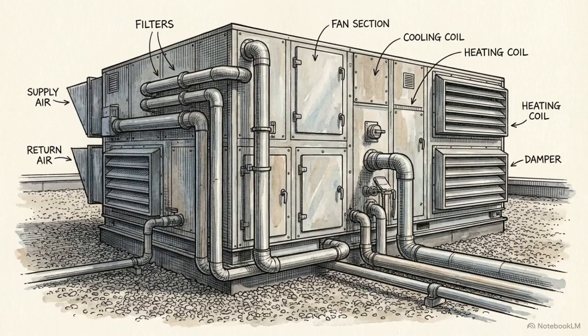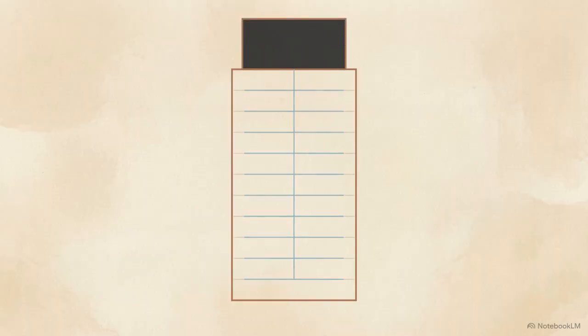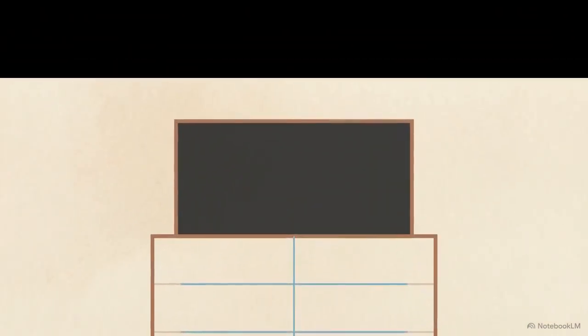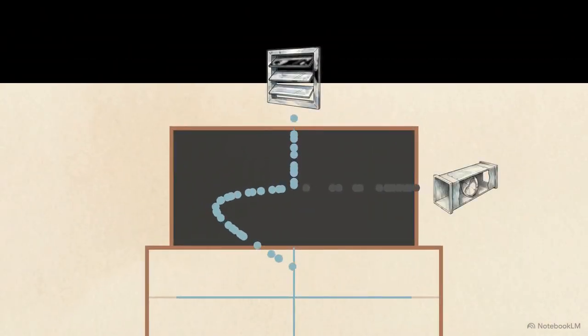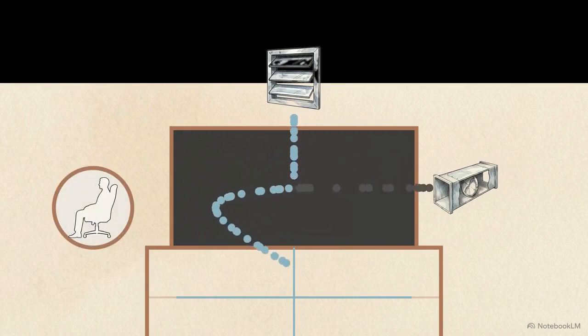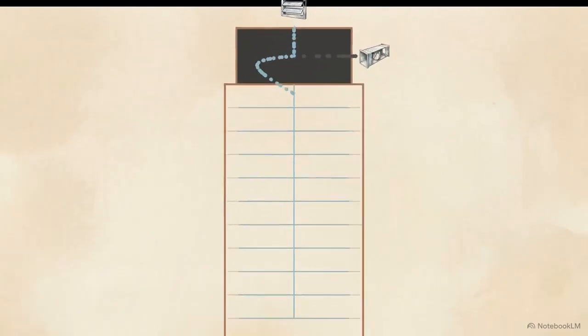Large commercial spaces rely on an air handling unit, or AHU. You can think of this massive piece of machinery as the central respiratory system, the lungs of the entire building. It starts at the mixing box. The AHU pulls in stale return air from the hallways and offices, blending it with fresh air from outside. This precise mix guarantees the oxygen levels stay high enough that occupants do not become lethargic from carbon dioxide buildup.